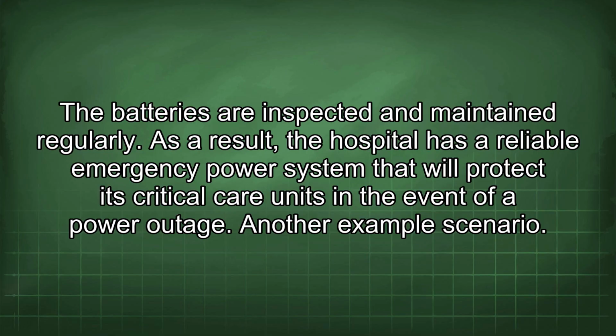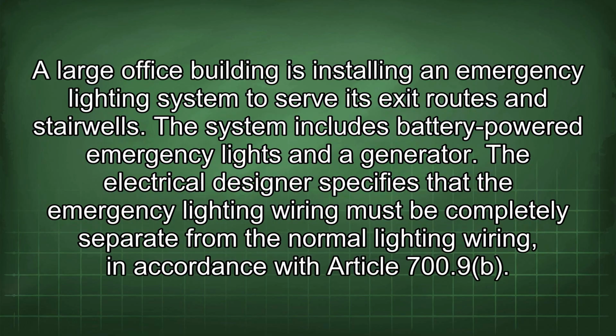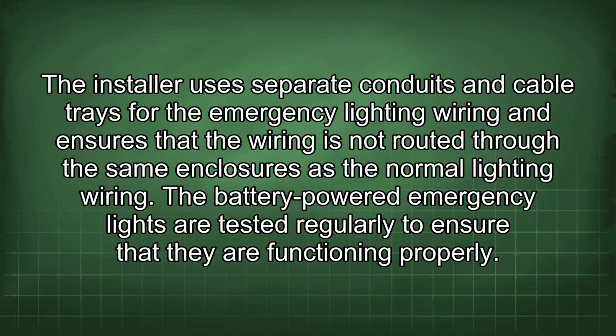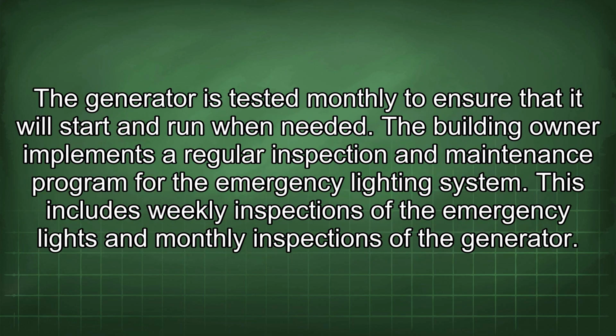Another example scenario. A large office building is installing an emergency lighting system to serve its exit routes and stairwells. The system includes battery-powered emergency lights and a generator. The electrical designer specifies that the emergency lighting wiring must be completely separate from the normal lighting wiring, in accordance with Article 700.9 B. The installer uses separate conduits and cable trays for the emergency lighting wiring and ensures that the wiring is not routed through the same enclosures as the normal lighting wiring. The battery-powered emergency lights are tested regularly to ensure that they are functioning properly. The generator is tested monthly to ensure that it will start and run when needed.